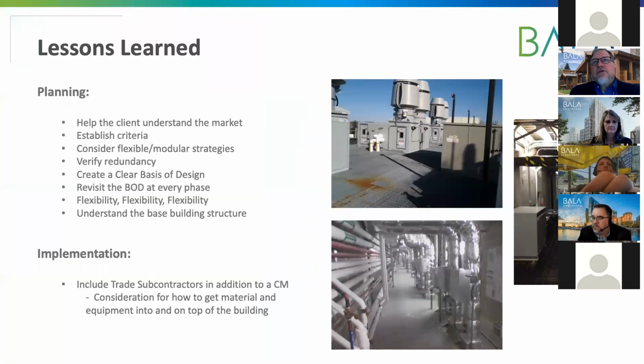And then here on the roof, you're going to see more stormtroopers, that's our exhaust system. Down in the bottom left, when Scott was talking about the low floor-to-floor height issues, and there's a way to do it with side mechanical spaces, this is what he's talking about. So on a building with low floor-to-floor, you can have the labs to the left of that piping rack where they're currently designed, and all the piping utilities are racked along the wall. All of the exhaust and supply VAVs are on the right-hand side, in a service corridor that goes up and over into the labs to serve the lab space.